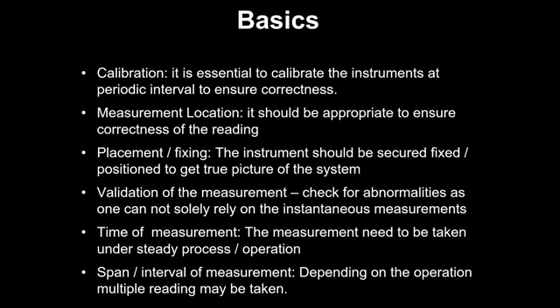The straight length specified by the manufacturer is normally about 15D before and 5D after the measurement, that is, 5 times the diameter after and 15 times the diameter before. So slightly here and there is acceptable. But in this particular case, the straight length was very small, maybe 3D or 4D. So I told them that it is not possible to do the measurement at this point. What we could do is this: the cooling water return line was again underground, and there were 10 or 12 risers feeding the water to the cooling tower top, where the diameter was marginally less and straight length was available.